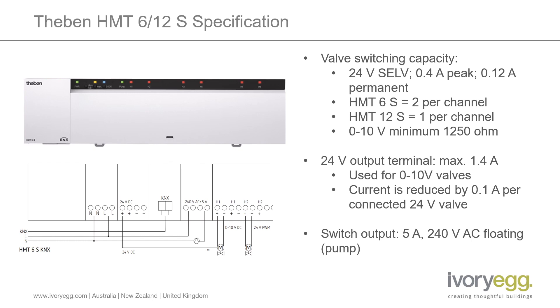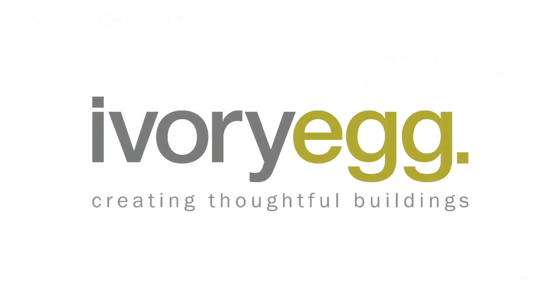The switch output, which is used for the pump, is a volt-free contact rated at 5 amps, 240 volts, so you will need to power that separately. The Theben HMT6S and 12S really are unique products. They have a lot of additional functions that you just don't find on other manifold controllers. It's great to see that they've listened to some feedback from the market, in terms of things like integrating the relay output. There are also some additional parameters that make sure the product works correctly with different types of manifold configurations. So really a good go-to product, super easy to install with everything self-contained. For more information, check out the links below and get in touch with the Ivory Egg sales team if you want some help specifying this product on your next project. Thanks for watching!